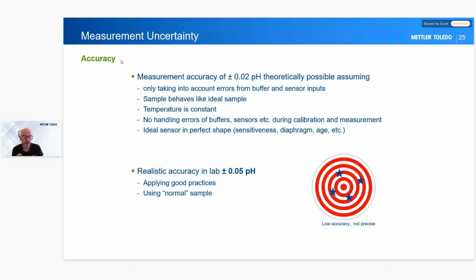The last thing is when we're selling pH meters, we're very good at marketing them and saying the meter itself will read down to 3 decimal places. But in reality, with the system and everything else involved, although we can take that 3rd decimal place as a reading via millivoltage, actually making that last decimal place repeatable is not possible because of the types of influences we have in the system already. So even though you buy a 3-place pH meter, it's only ever going to read, at best, repeatability-wise, down to plus or minus 0.05 of a pH.